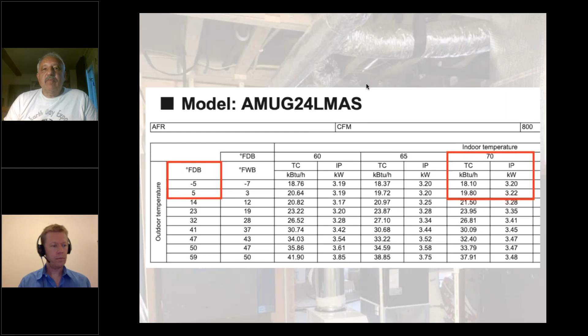One of the big questions that you'll get into as you start to explore heat pumps for your clients is how cold can it be outside with heat pumps still working? There's of course a common misconception that heat pumps stop working at freezing, at 30 degrees or 32 degrees. And that's just not true. They do keep working. And the more advanced cold climate heat pumps speed up their compressor speed to continue with substantial heat output, even at very cold temperatures. So each manufacturer is a little bit different.